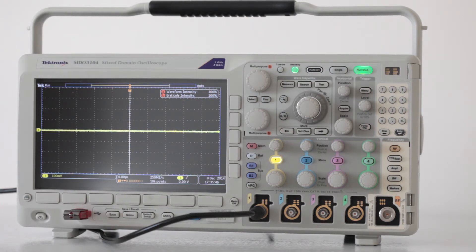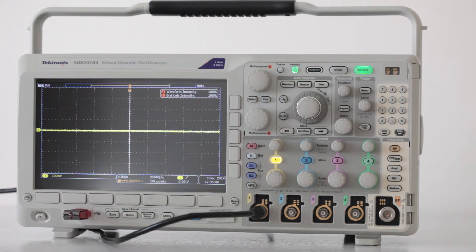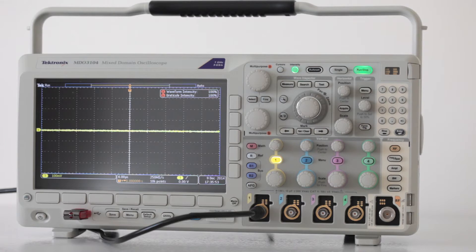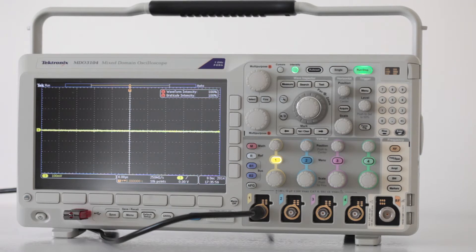The arbitrary function generator has been installed in this instrument, and we've connected a BNC cable from the AFG output on the back panel to one of the four analog input channels on the front panel.